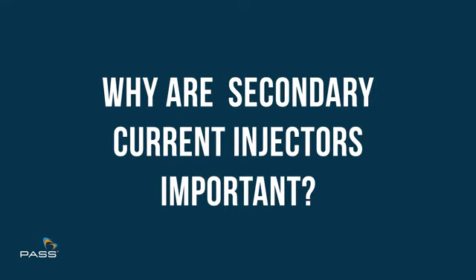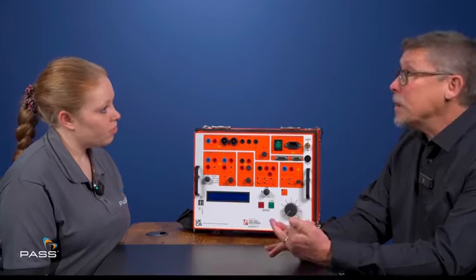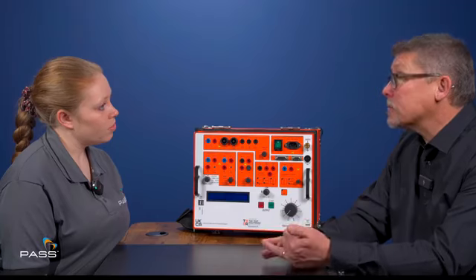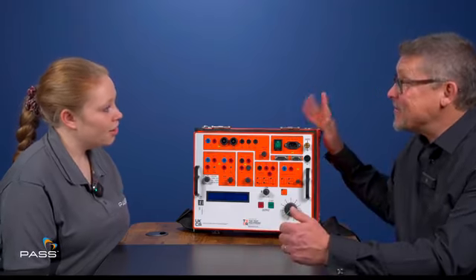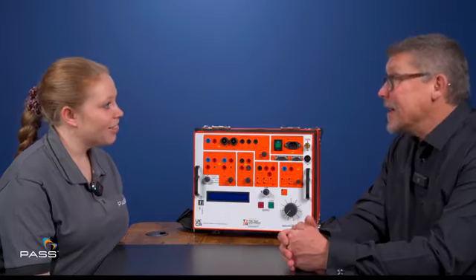Right. So why are secondary current injection testers important? Literally just to test the relays. The relays are the things that protect your expensive plant within a substation. So you're going to have a transformer. That's an expensive outlay. And if you was to overshoot that transformer or overrun that transformer and burn it out, you could be looking anywhere up to £500,000. So for the sake of a little 10 grand unit to test the relays to protect that circuit, it's a good investment. But they won't need to be told that.